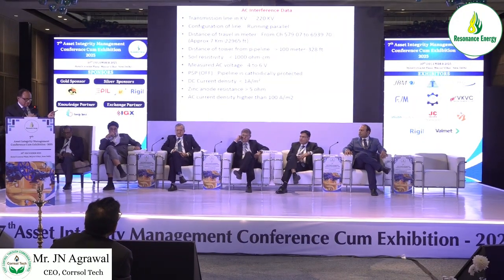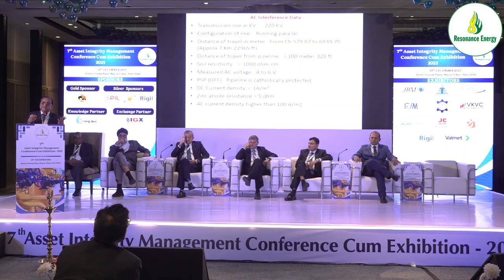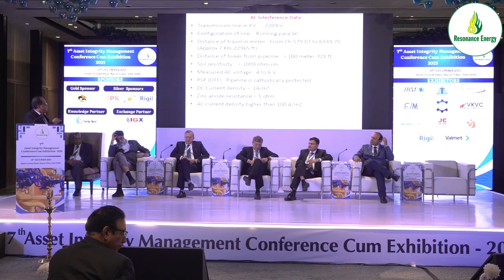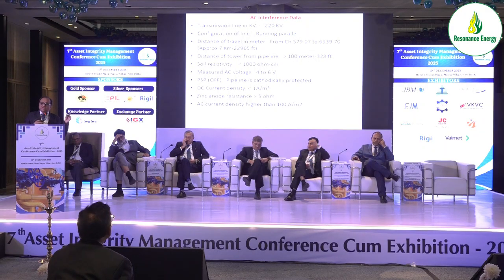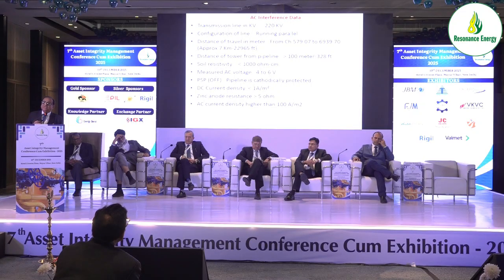This is the AC interference data, which is important. A 220 kV line runs parallel for 7 kilometers. The parallelism length is what makes the pipeline more susceptible to AC interference and AC corrosion. So 7 kilometers. The distance of the tower from the pipeline was 100 meters. Now they are talking about 25 meters. Even the Canadian study says that even at 100 meters, on average, susceptibility to AC corrosion is there. So you have to go around 300 to 500 meters as far as you can. Of course, it is not always possible now, but if it is possible to route the pipeline away from the transmission line, you have to. This is the fact. Then soil resistivity is low. An AC voltage of 4 to 6 volts is sufficient to cause, at 1000 ohm centimeter, an AC current density of more than 100 ampere per meter square.